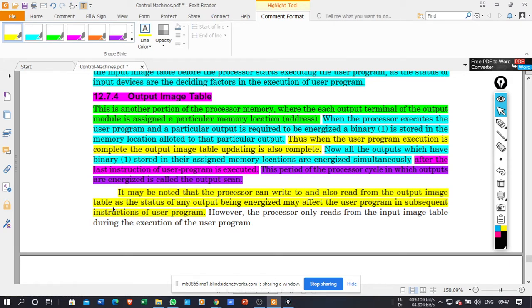So both functions are done by the processor: it will write to the output image table, as well as read from it. However, the processor only reads from the input image table; it does not write to it. This is the major difference between the input image table and the output image table. The output image table can be used for both reading and writing by the processor, while the input image table can only be read from.